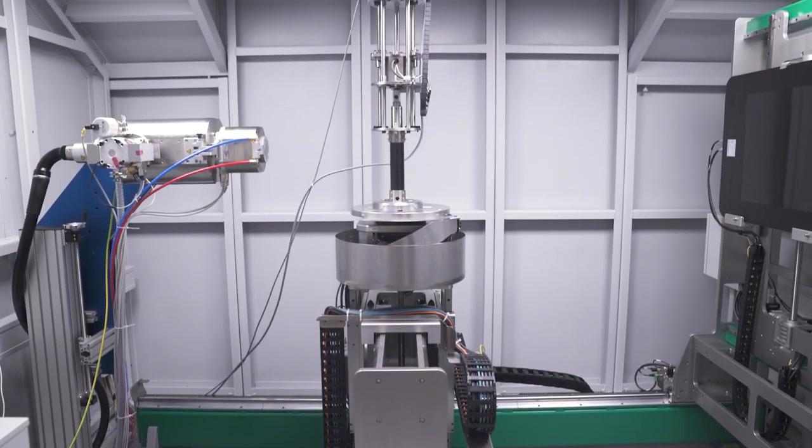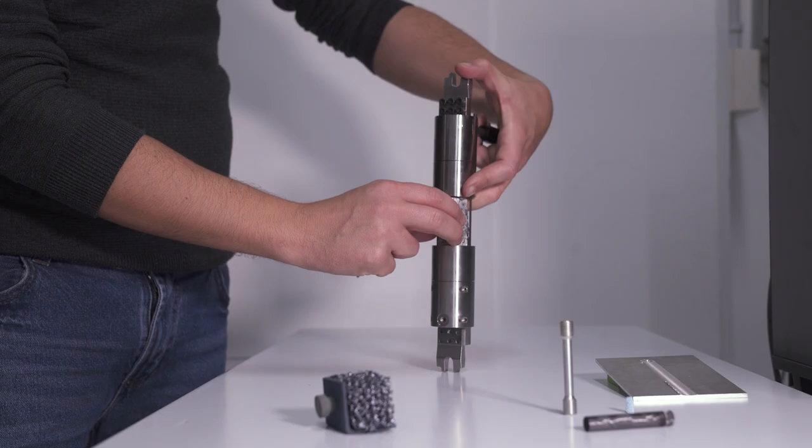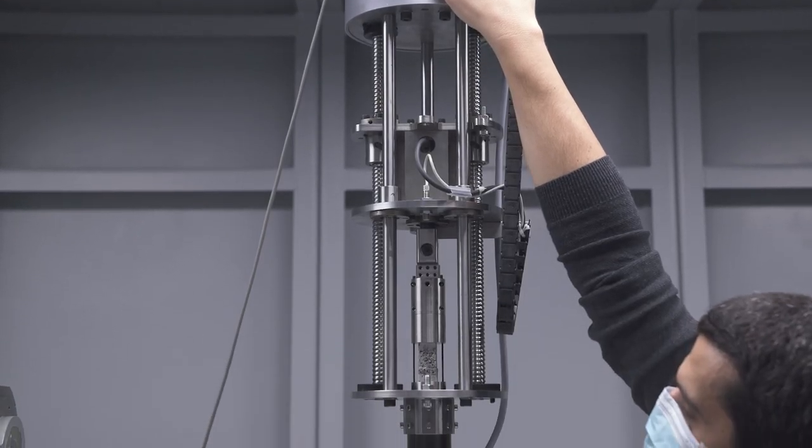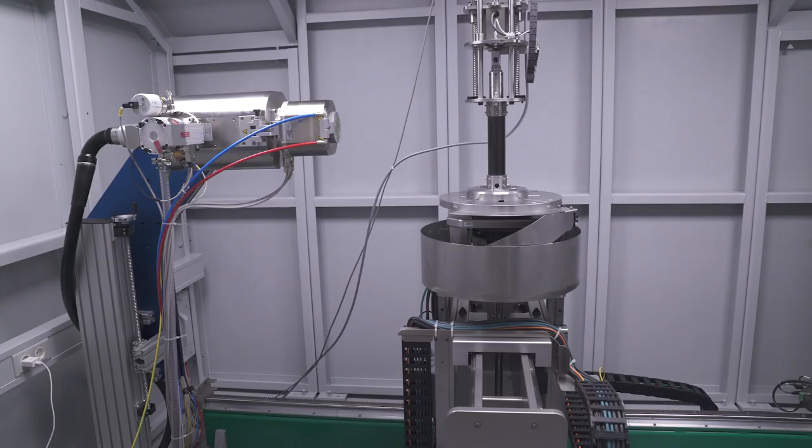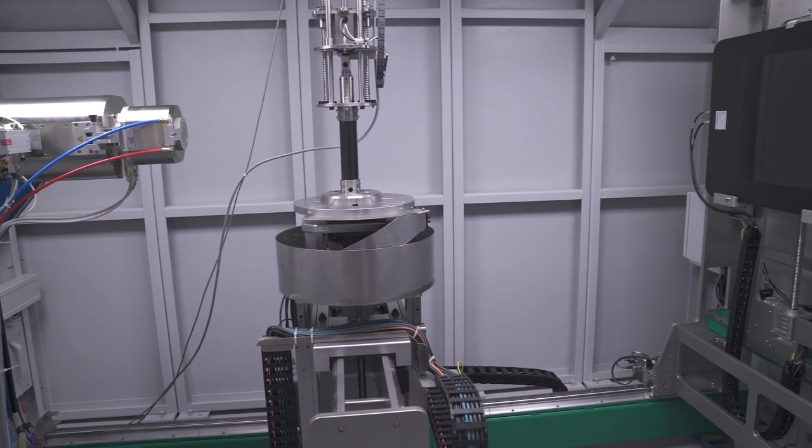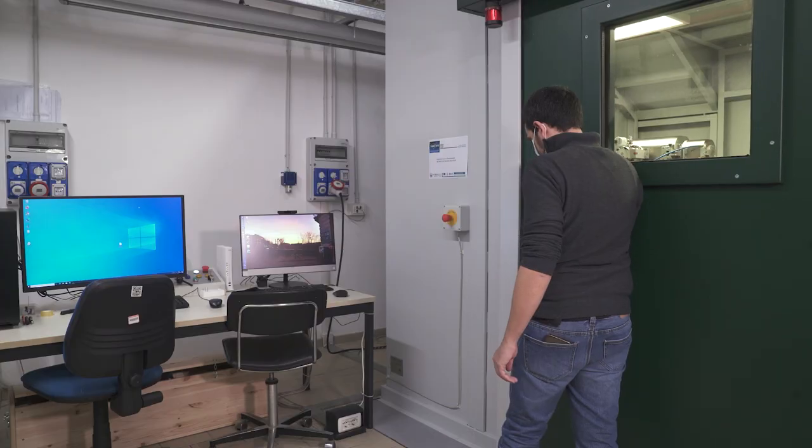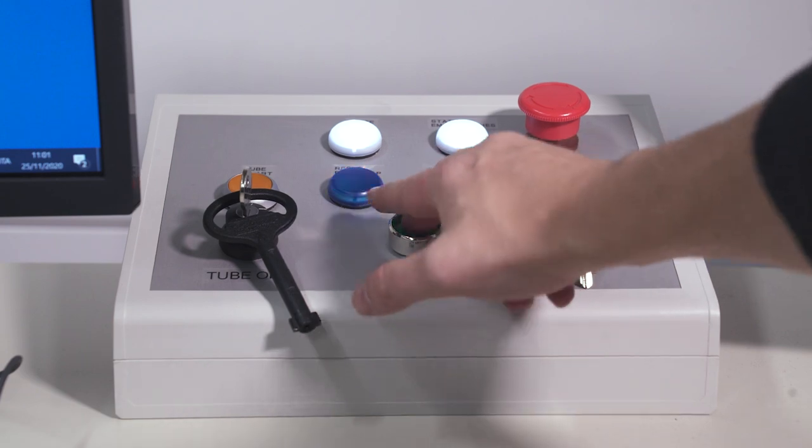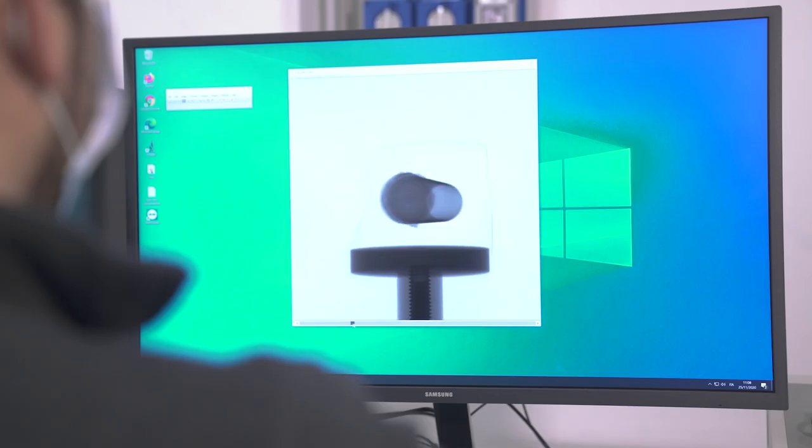Custom-built computer tomography with in-situ mechanical testing: tensile, compression, bending with a loading cell of 10 kN. With a chamber size of 3.5 m x 2.5 x 2.5, able to scan samples up to 0.5 m x 0.5 x 0.5 with resolution of about 5 microns.